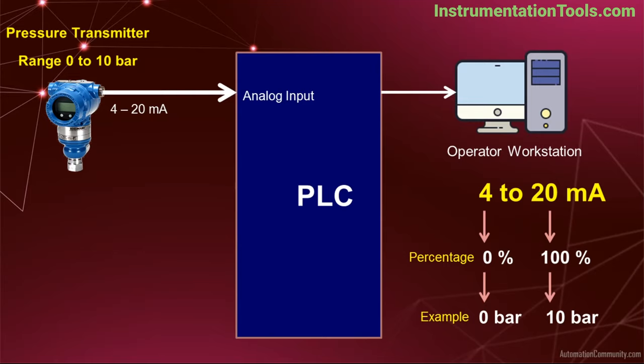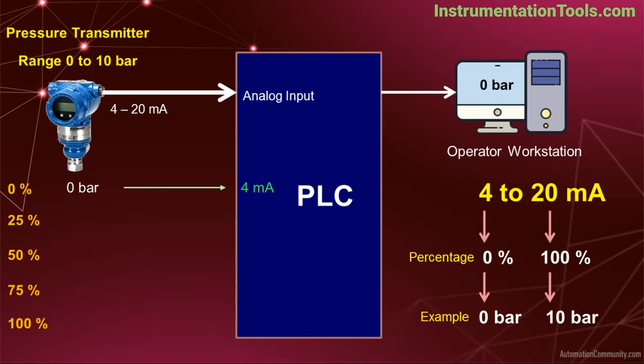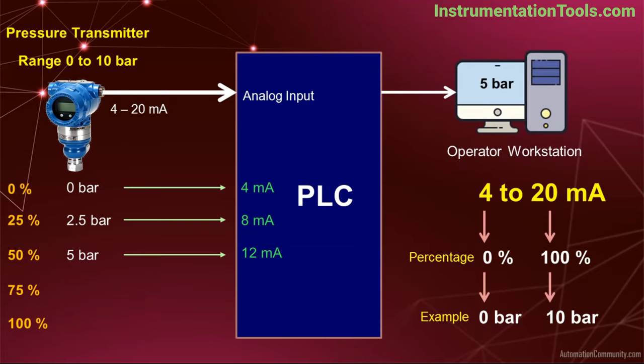Apply the process pressure in terms of 0%, 25%, 50%, 75%, and 100% to the pressure transmitter. If the process pressure is 0 bar, the transmitter sends 4 mA and the PLC displays 0 bar. At 25%, that is 2.5 bar, it sends 8 mA and displays 2.5 bar. At 50%, that is 5 bar, it sends 12 mA and displays 5 bar. At 75%, that is 7.5 bar, it sends 16 mA and displays 7.5 bar.